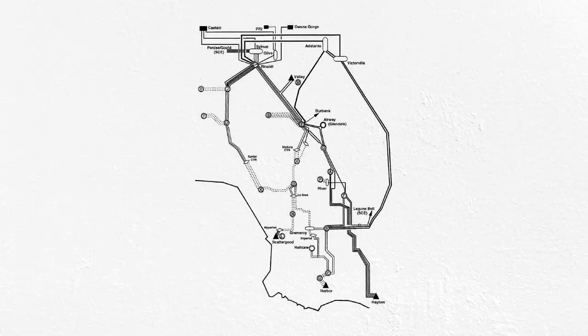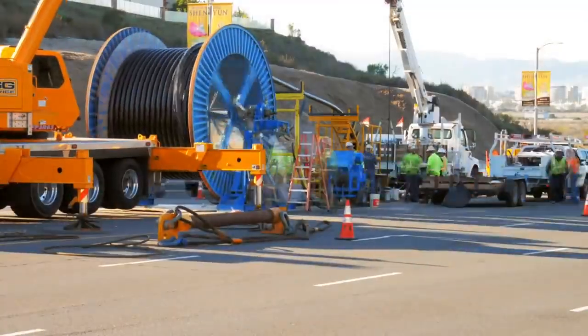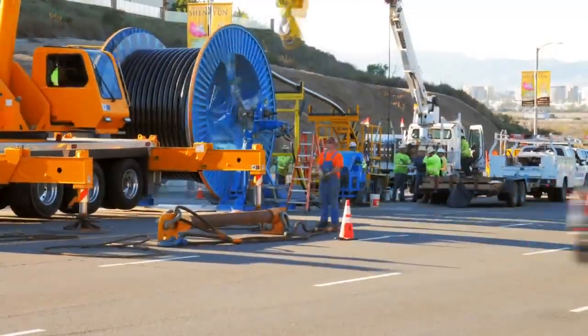3 230 kilovolt lines, one for each phase, would deliver enormous amounts of electricity over the approximately 10-mile or 16-kilometer distance in West Los Angeles, powering hundreds of thousands of homes and businesses. However, putting high-voltage lines below the ground created a whole new set of challenges. When strung across towers, the conductors at this voltage each require around 10 feet or 3 meters of clearance to avoid arcs. The air is the insulator, doing the job of keeping electricity constrained within the conductors.